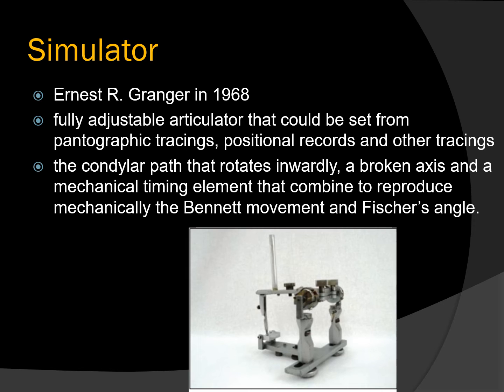It has a broken axis and also a mechanical timing element, which combine to reproduce mechanically the Bennett movement and also the Fischer's angle. The condylar path locks can be released in the simulator so that the upper member can be separated from the lower member, and the incisal guide pin was curved. So these were the features of the simulator, which is a fully adjustable articulator.